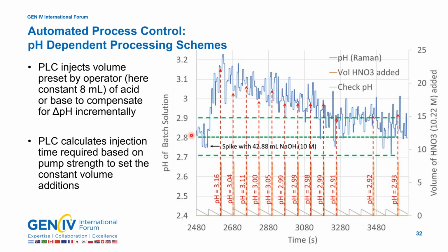So we start here within the control pH zone. We spike the solution with sodium hydroxide to push it outside the control zone on purpose. At this point, the PLC controller activates, and each one of these orange lines that I have indicated is when the PLC controller actuated and injected some acid to drive the pH lower and lower until we get down within the control zone, and the automatic PLC controller stops delivering acid. And then it does get into the control zone and stays there through the experiment.